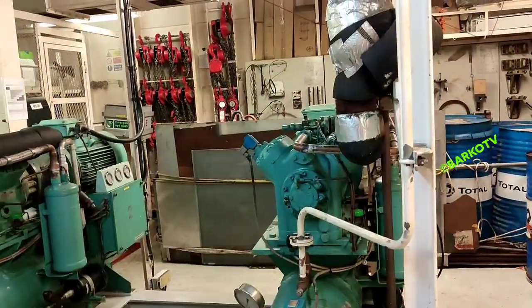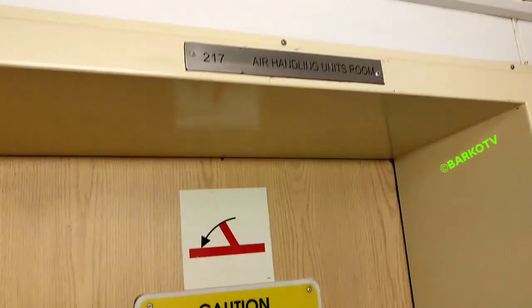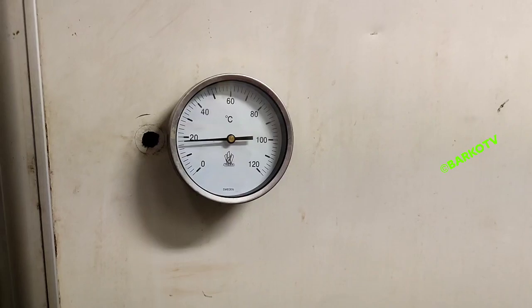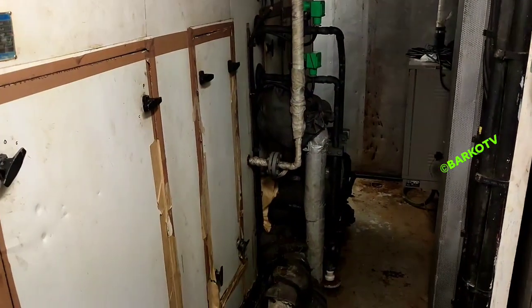That is the reason: if the evaporator is clogged or restricted with dirt or rust, you will get ice formation because there is no airflow. We are here at the handling unit — the temperature is 17°C and it is running smoothly. We plan to clean this up thoroughly. Thank you for watching — don't forget to like, share, and subscribe for more videos. Follow us on Facebook — Barko TV. Adios!